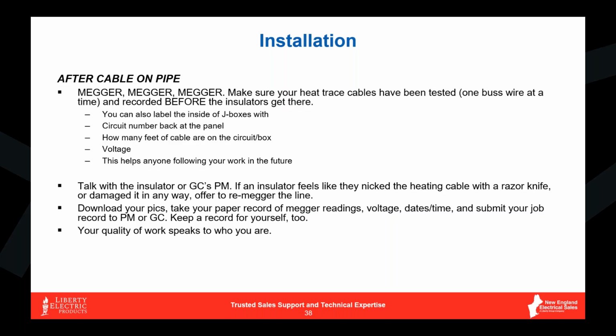We Megger tested everything. We voltage checked everything. We resistance tested everything. We have pictures of our terminations. We have pictures of our installation. It's going to be $250 for me to get out on site, per hour. And the soonest I can get a guy there is a week from now. It just kind of changes the dynamic of that. So always remember, cover yourself in the install.